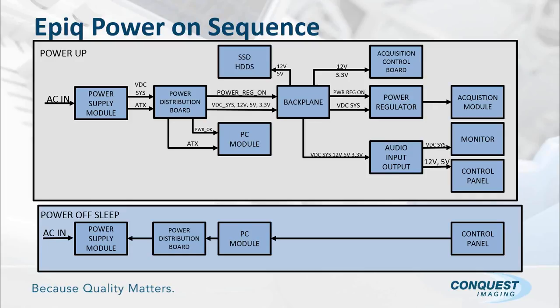At that point, if you move back up above that to the power regulator board, it simply goes to the acquisition module, which is your front end, and powers the front end up. So that's your power on sequence. As you can see, it's just not that difficult. There are not a ton of different voltages going on, and the signal flow is pretty straightforward. So pretty nice system to work on, and we will get into some troubleshooting techniques for the power supplies.